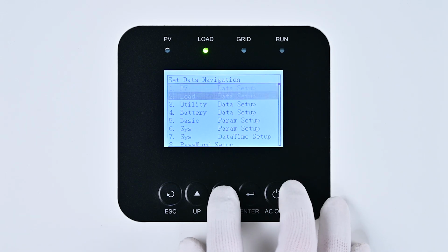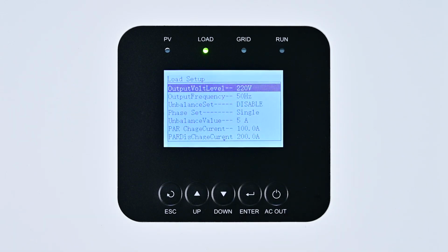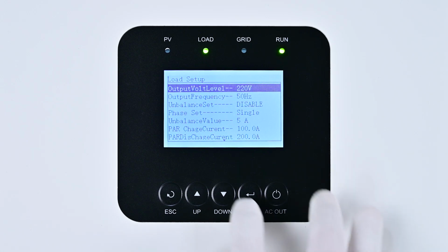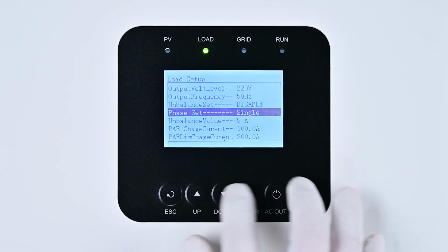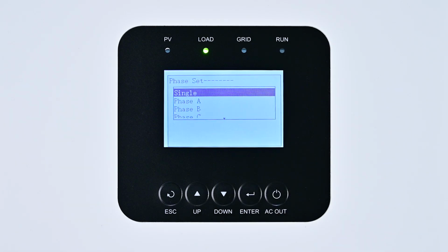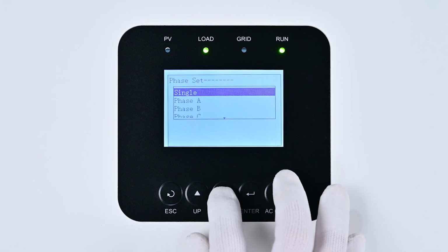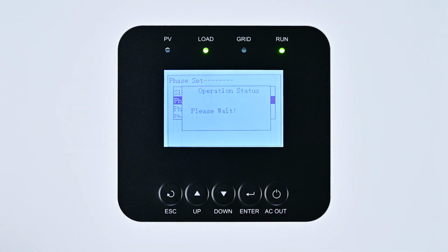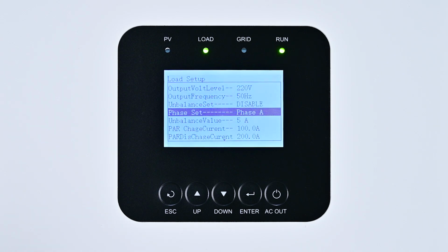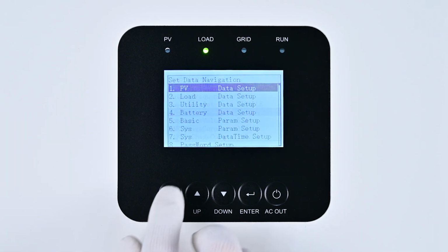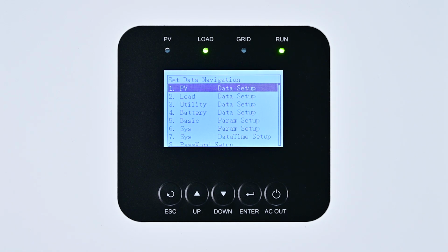Use the down key to select the load option and press Enter to enter the load setup interface. Continue using the down key to reach the phase set option and press Enter to enter the phase set interface. The default setting is single. Since this setup is for three-phase operation and this is the first device, it needs to be set to phase A. Do this by navigating to phase A, using the down key and confirming with Enter. Finally, press ESC to return to the Set Data Navigation interface.